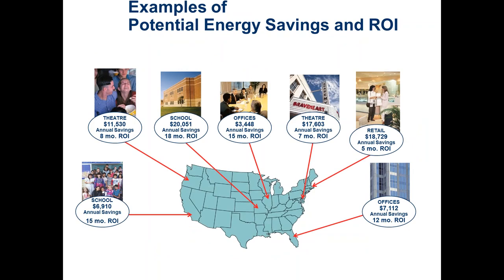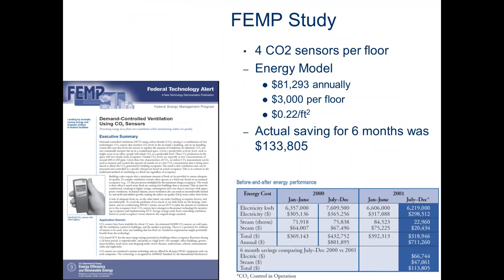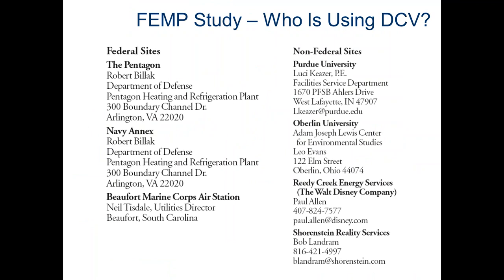The key is to find building types with large outside air requirements and variable occupancy. A 911 call center is not a good DCV candidate — those people need to be there continuously. Schools and theaters are among the absolute best candidates. AMC Theaters started doing this 15 years ago because of the savings potential. There are case studies showing $130,000 savings for half a year on large projects, and now there are thousands of buildings with demand ventilation systems installed across the United States.